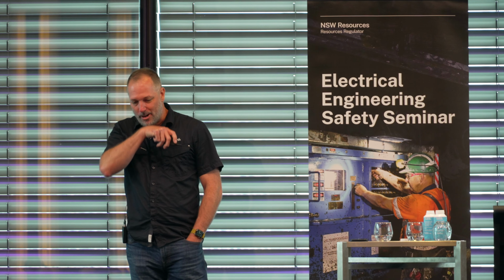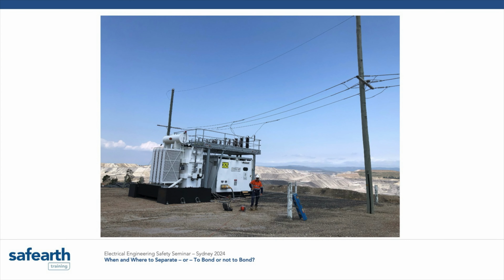Here's an interesting little photo of a little transformer sitting on an open cut side of a hill. The overhead earth wire, which you can see running over the top, probably isn't connected into the earthing system. It may be, but on face value, you're probably looking at it thinking, well, the designer here decided I'm going to provide lightning protection for the asset and I'm going to keep the system separated because it's got a trailing cable. The trailing cable, in this case, probably doesn't go underground, but it might go across to a piece of equipment, powering it, dragline or whatever it is, or a bucket.